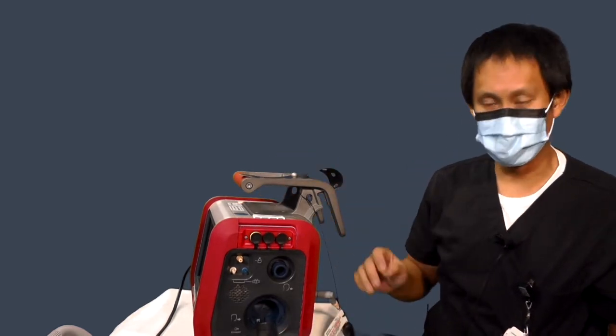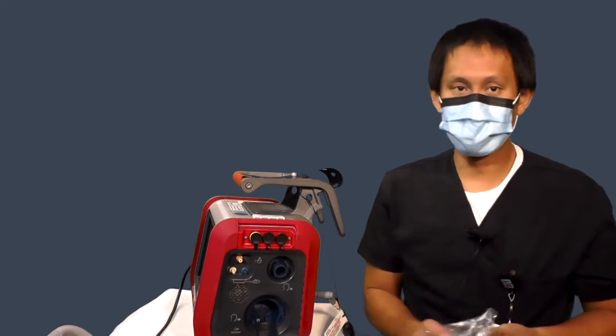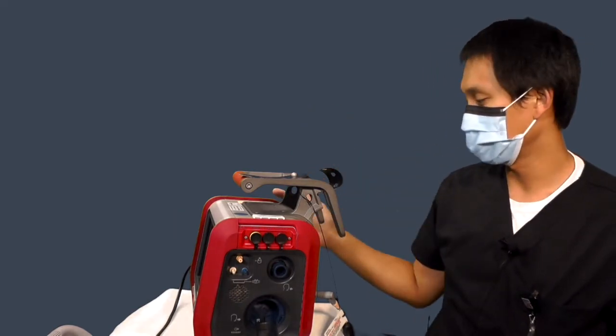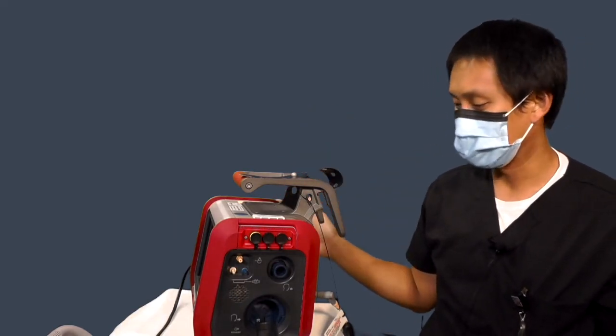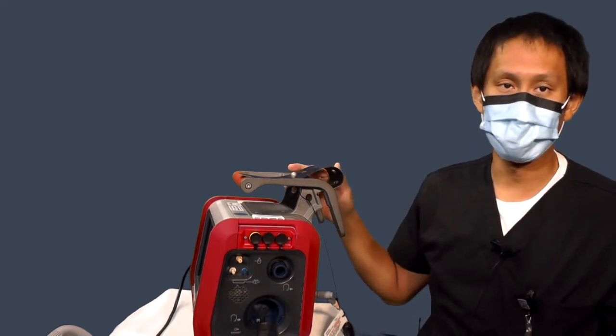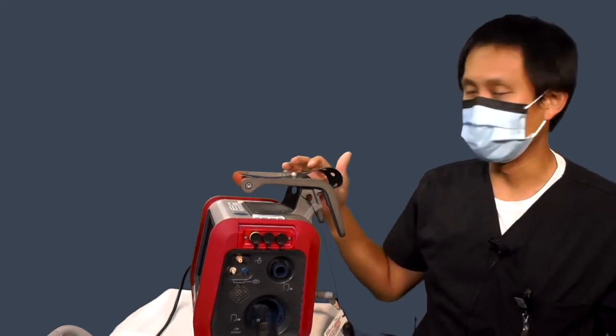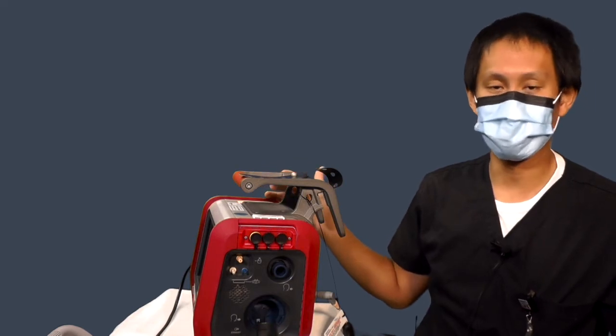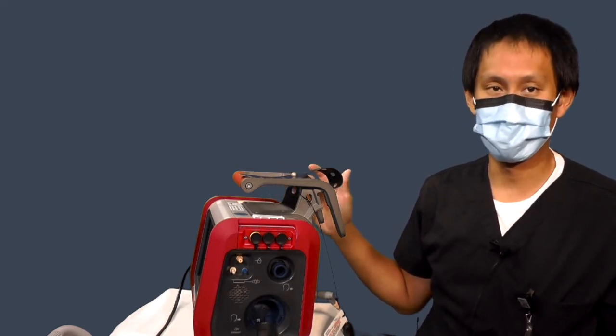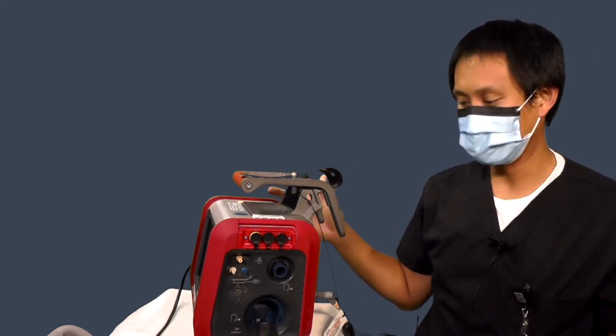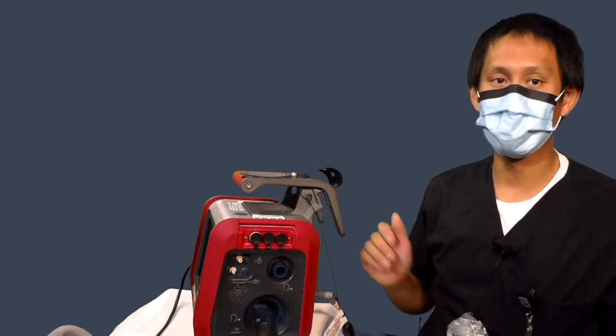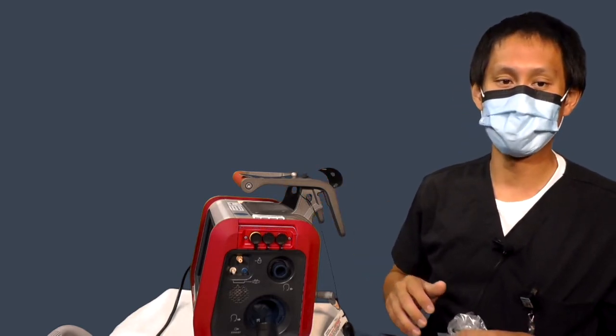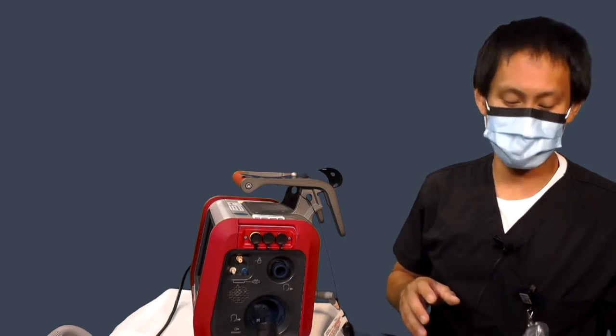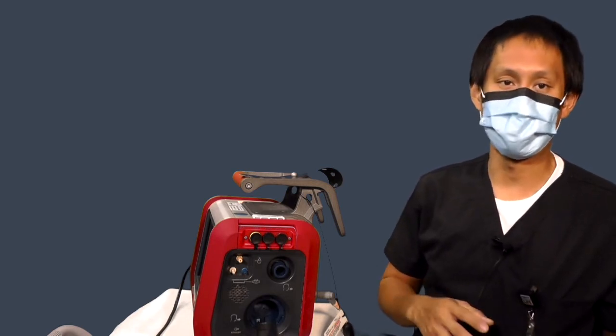Okay, so let's get this set up. Up until this point, everything does not come apart. So when you go on a transport and you come back, all you do is wipe it down with a hospital-approved cleaner per the manufacturer's dwell time, and it's good to go. Everything after this point, so the ventilator circuit and the exhalation valve, will be tossed.